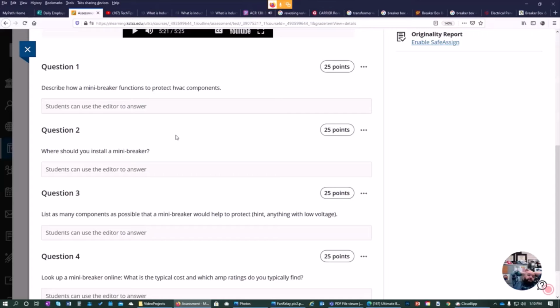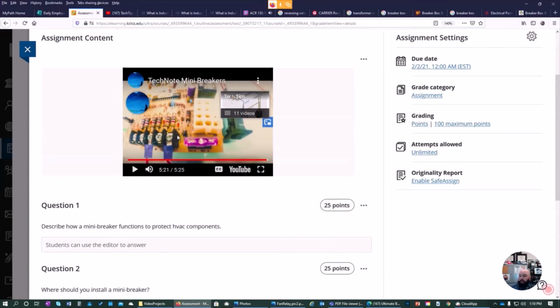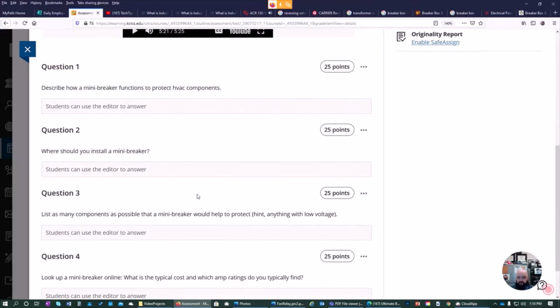rubs through and touches the cabinet of the equipment. Remember, it could touch on the outdoor unit and trip the fuse on the inside, because the control voltage for your outdoor unit starts at that indoor transformer 90% of the time. So they're great, mini breakers. They're resettable. These fuses are one-time blown.